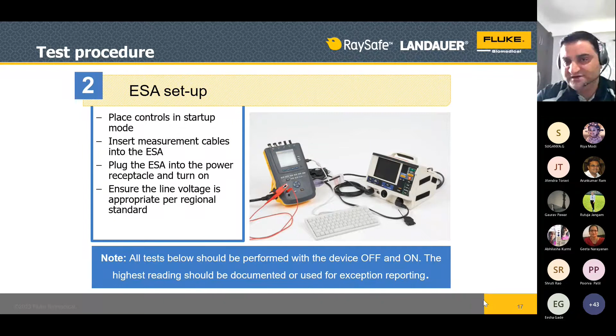For ground wire resistance, you have to connect this crocodile red color probe to an accessible part of the earthing. Then you can very well see how much the ground wire resistance is. Accordingly, you can see the mains voltage, whether the mains voltage is correct or not, whether earthing is proper or not. Our equipment can detect all those things.